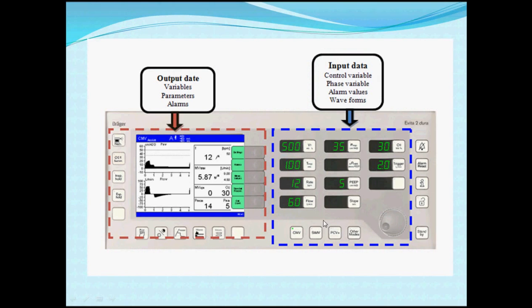Depending on the selected mode — for example, pressure-controlled mandatory ventilation — the relevant settings become active. You fill in values such as flow (e.g., 60 or 40 L/min), respiratory rate (12, 10, or 15 breaths/min), inspiratory time, tidal volume, PEEP, triggering, and more. These data are filled according to the patient's physiology, pathology, body weight, and clinical requirements — especially to control carbon dioxide and oxygenation.